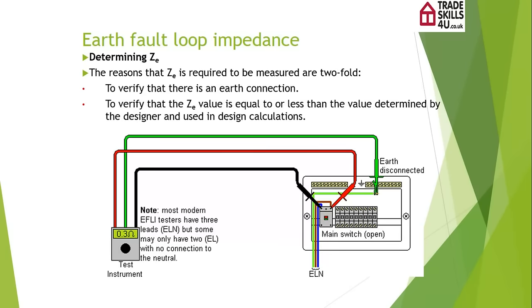Here's the installation. This is the origin of the installation — the distribution board or consumer unit that is at the origin. As you can see, we're going to disconnect the main earthing conductor. We have to make sure that the installation is safely isolated, as removing the means of earthing would be very dangerous if we hadn't isolated the installation.